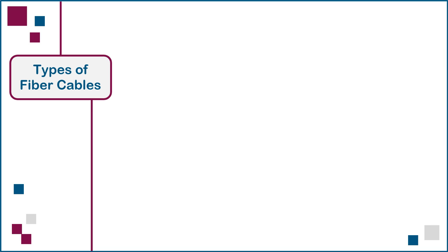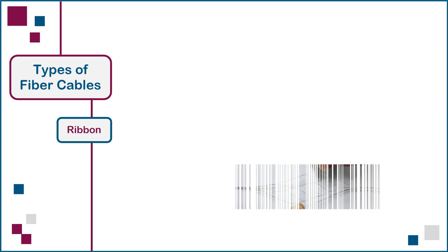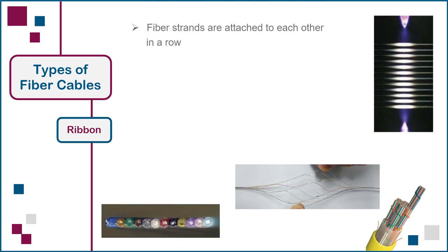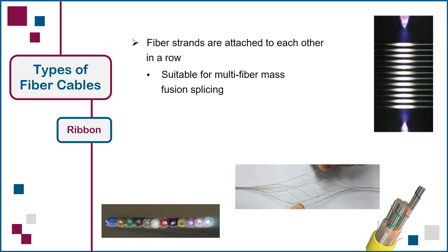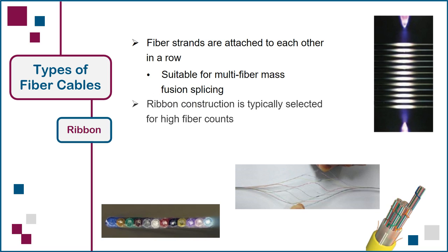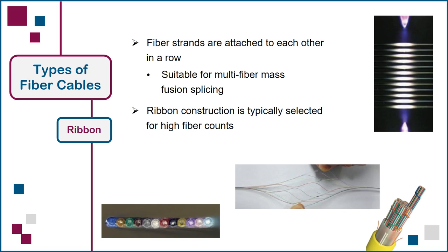The third type of cable construction is ribbon, where the fiber strands are attached to each other in a row, creating a flat or pliable strip of fibers suitable for multi-fiber mass fusion splicing, as shown here. The ribbon construction is typically selected for high fiber counts, all the way up to 6912 strands in a single cable. Note that the highest densities numbering in the thousands are typically associated with data center and service provider facilities.